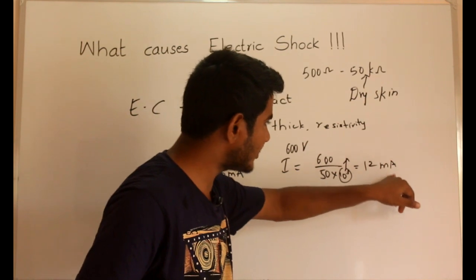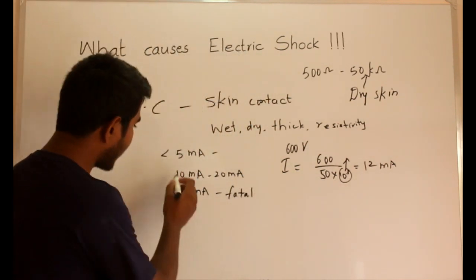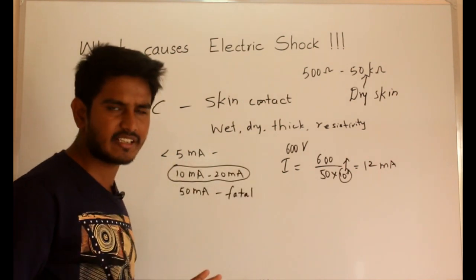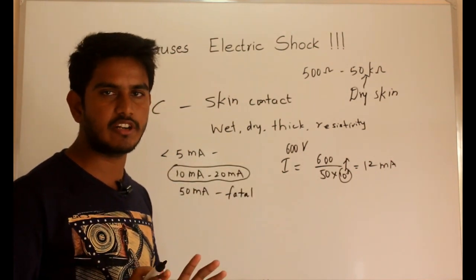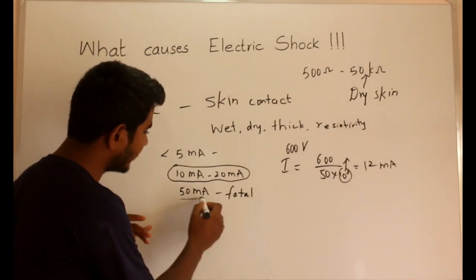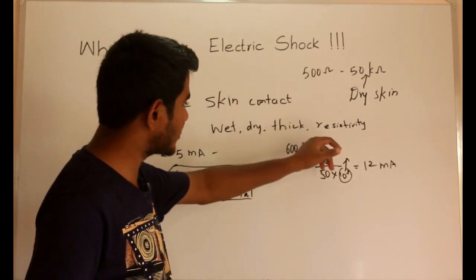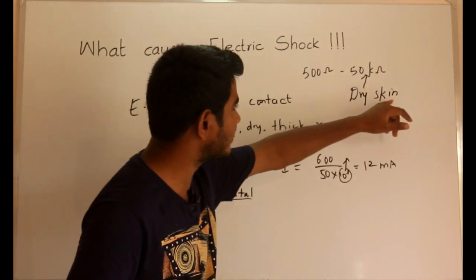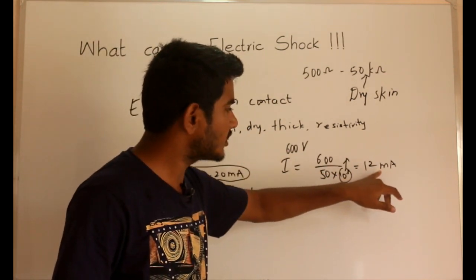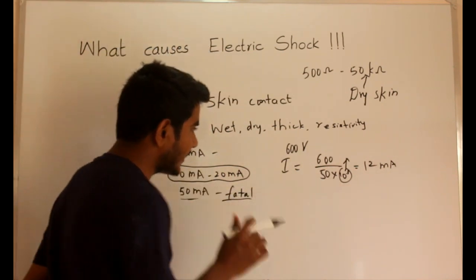That gives us 12 milliamperes. So with a 600 volt line and dry skin, you will experience 12 milliamperes. This is not fatal, because currents between 10 milliamperes and 20 milliamperes are potentially dangerous — the victim loses muscular control — but they are not fatal. The consequences become fatal only when the current exceeds 50 milliamperes. So a 600 volt line with dry skin may not be a fatal situation.